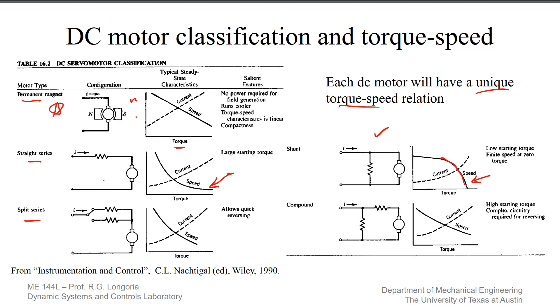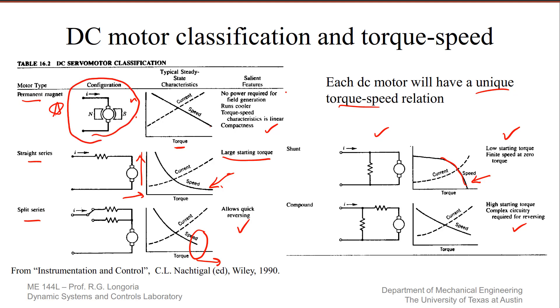Here's your straight series motor. Some of these have distinct advantages. One of the nice things about DC motors is they have really large starting torque — at zero speed you have high starting torque. This table shows some different qualities about each of these. Again, the advantage of a permanent magnet DC motor is that you don't need external power or any power going in to generate your field, which is formed by the permanent magnets attached to the housing.